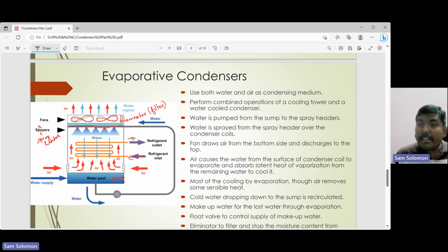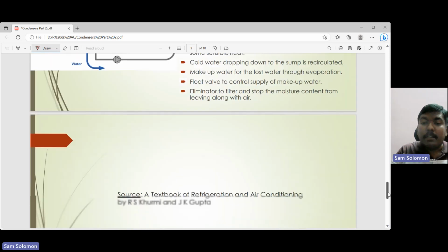Okay, so these evaporative condensers perform the operations of both a cooling tower, where you have the water being sprayed over the condenser, and also act as a water cooled condenser, because this water carries away the heat from the condenser surface. So your evaporative condenser acts both as a water cooled condenser as well as a cooling tower, and it uses both air and water as the cooling medium. Okay, so this is the end of condensers.